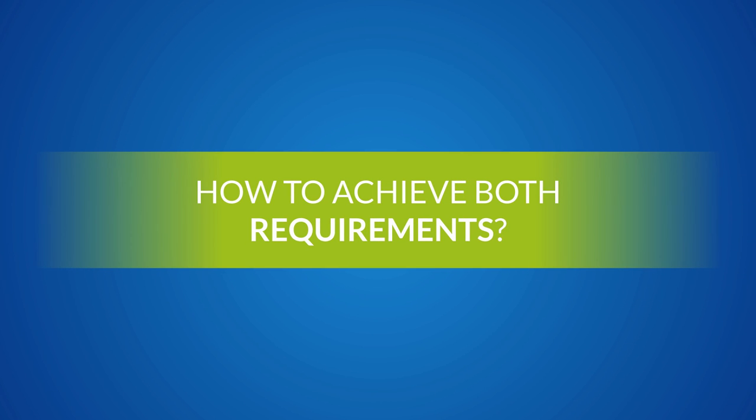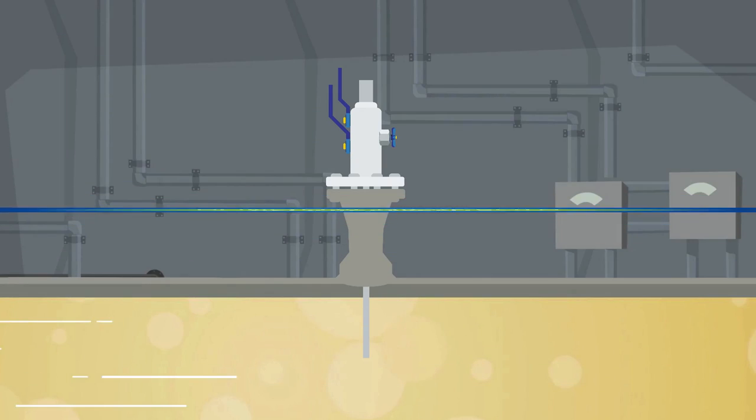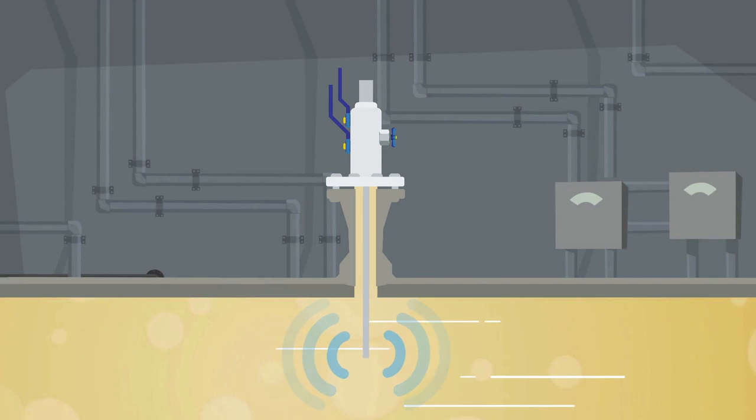How to achieve both requirements? To fulfill both purposes, the support collar needs to be fitted tightly within the flange. Any gap between the support collar and the flange wall gives space for vibration of the probe, which could lead to the break of the probe.